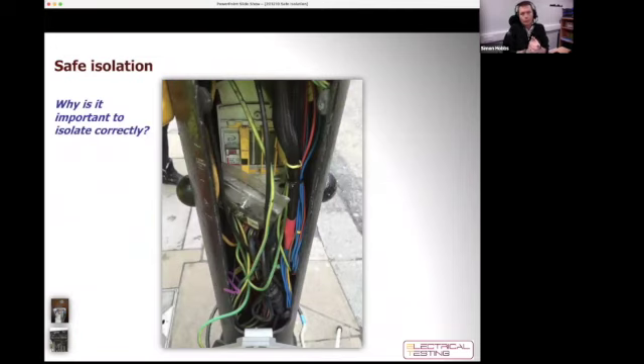So why is it important to isolate correctly? Well, here are a couple of pictures and scenarios. The first one is that we can't always be sure what the circuit is feeding, what equipment it's feeding. There's a lot going on in this street light. It may be that I switch off the main switch and everything is isolated, but it may be that I've got a back feed from somewhere else, a catenary wire feeding in at the top of the column and back down, who knows? So correctly isolating is incredibly important when working in an installation like this.